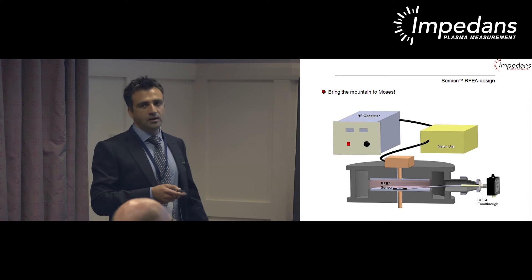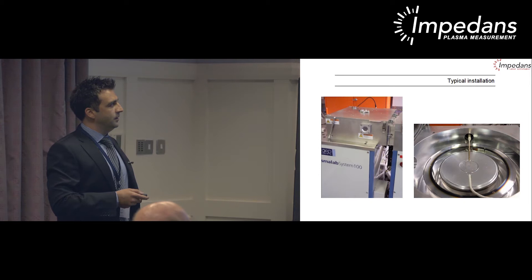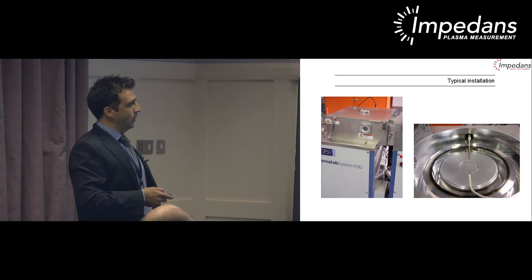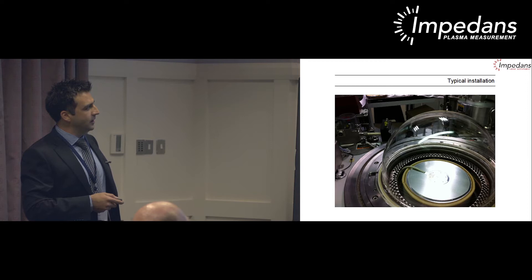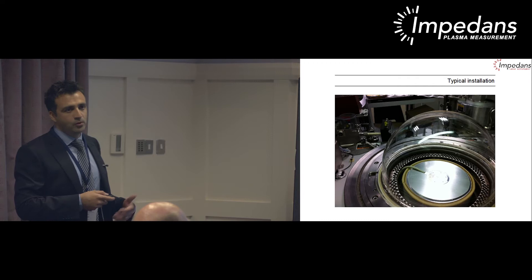A typical installation was demonstrated at Dublin City University in an Oxford Instruments etching tool, with the analyzer embedded in the powered electrode. Studies were also done in a Hitachi ECR etching tool—more complicated due to dielectric windows—but the retarding field analyzer was embedded in the electrode and signal cabling taken out through a vacuum feedthrough, which is quite convenient since Langmuir probes are very difficult to use in these types of devices.